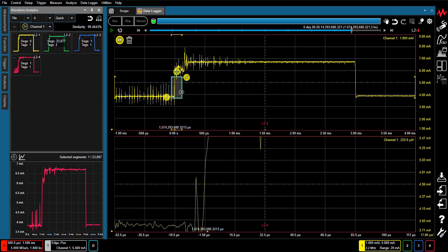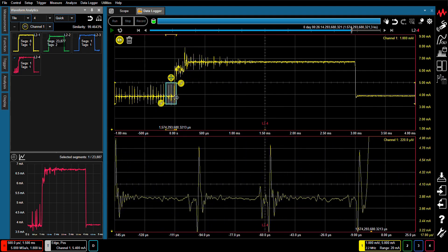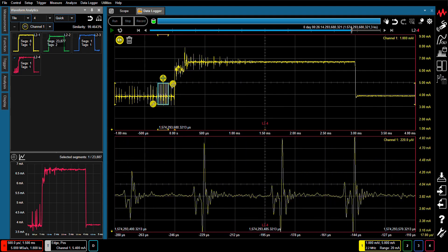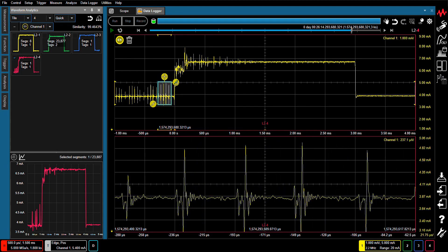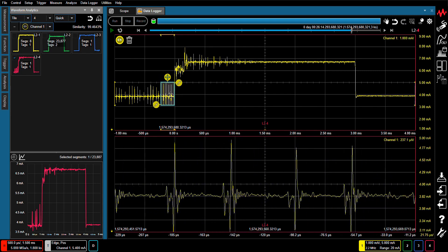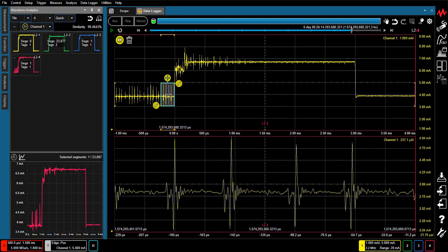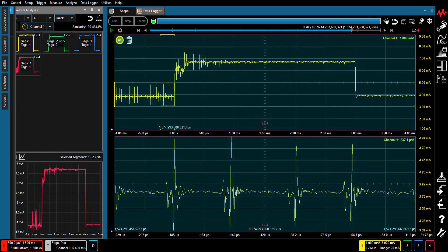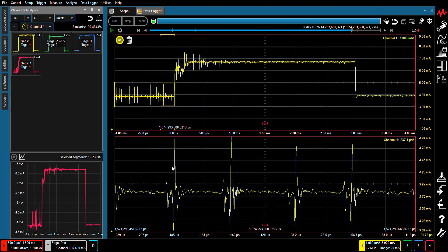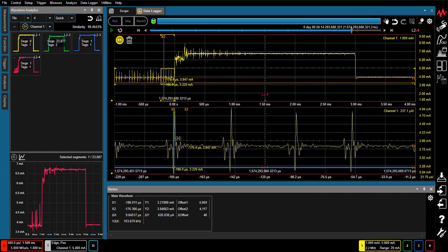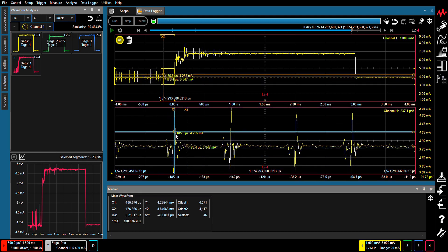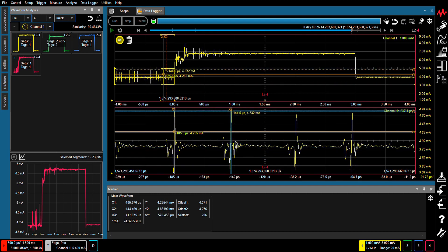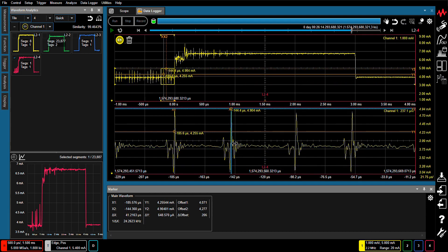The CX3300 can measure slight waveform differences precisely thanks to its low-noise nano-amp and microvolt resolution, which is not possible using conventional oscilloscopes. In addition, with its high-speed 10-megasample per second sampling rate, the CX3300 will not miss fast intermittent anomalous signals when making long-duration measurements.